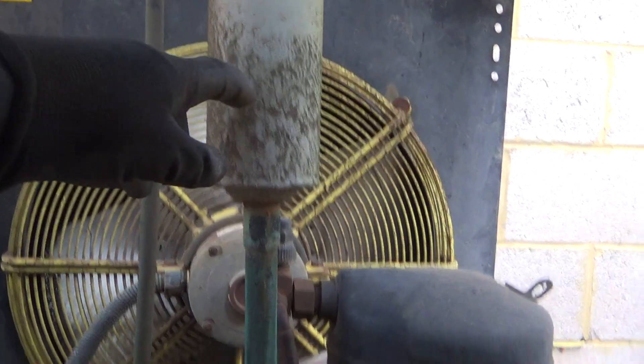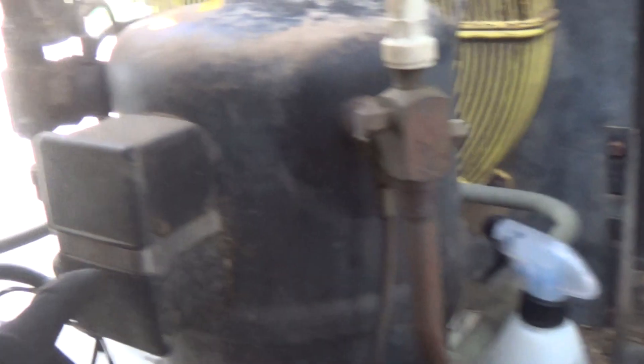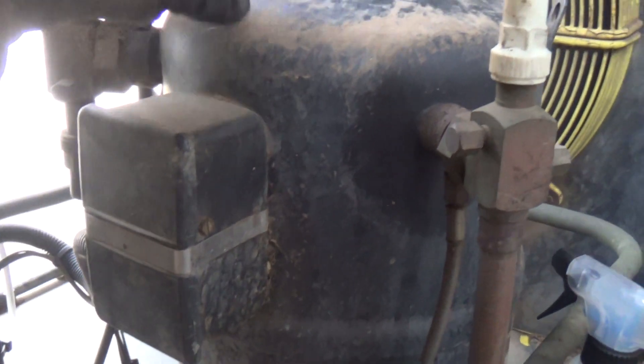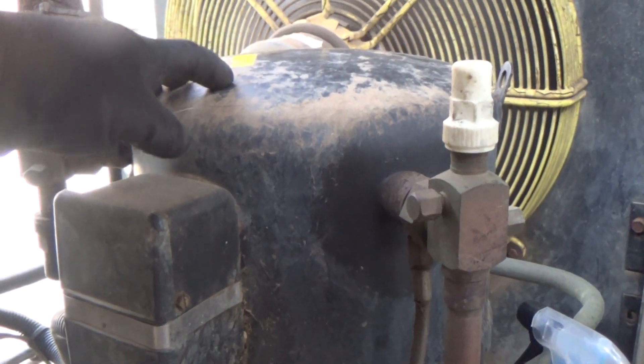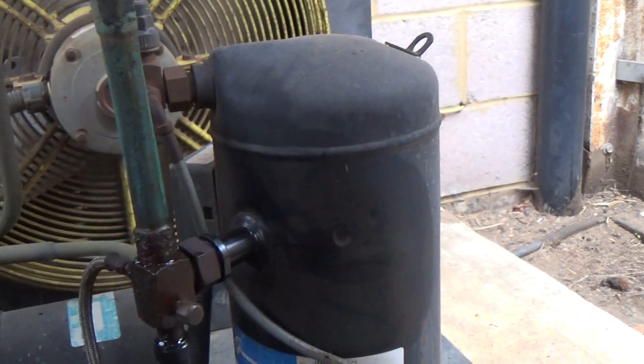We put a burnout dryer in there, so that must have been a nasty burnout. Originally they had these piston compressors in - these Copeland piston compressors - but these have been obsolete for years, so when they fail you end up having to put one of these scroll compressors on there.